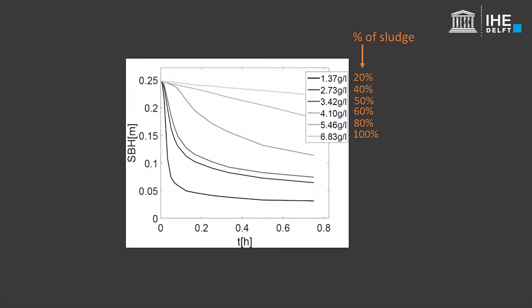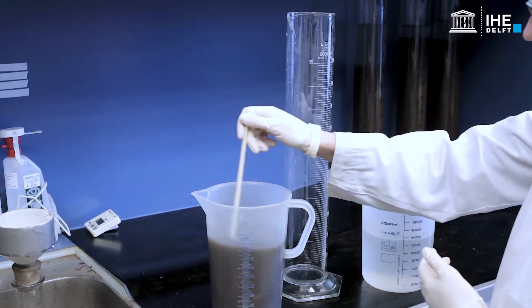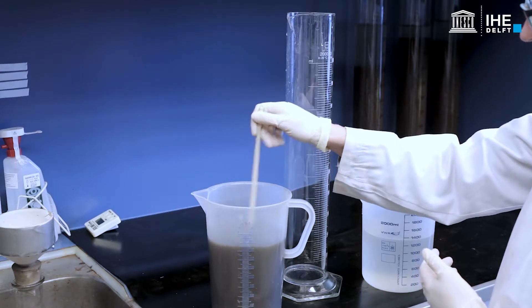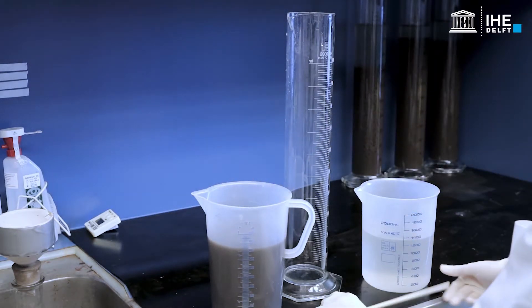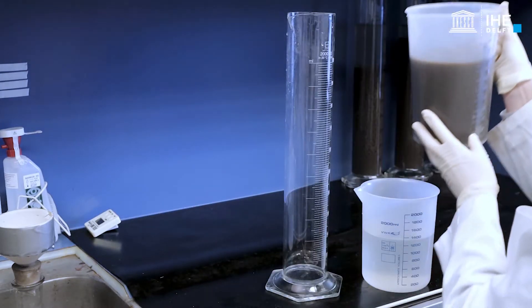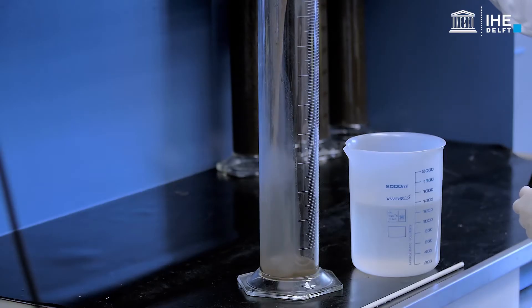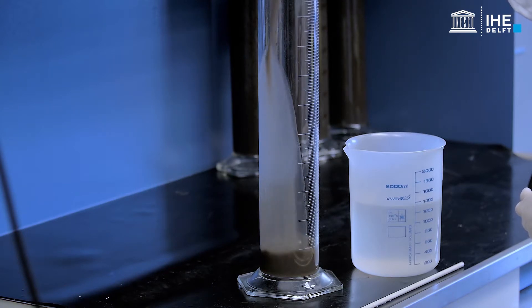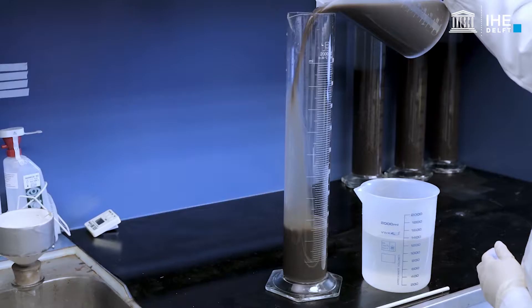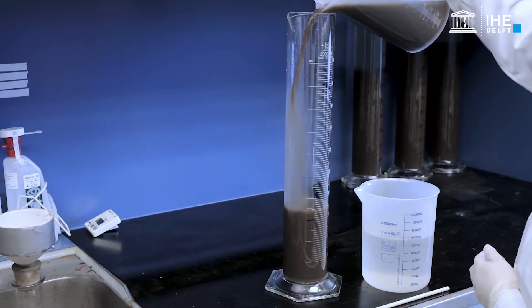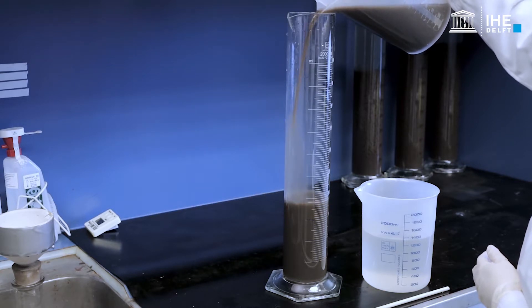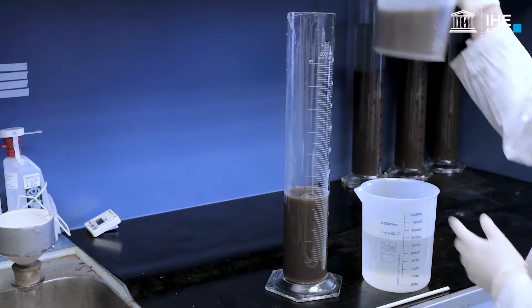To investigate the relation between settling velocity and sludge concentration, batch settling curves can be measured for a dilution series. A dilution series is made by diluting or concentrating sludge from return flow with effluent. For a 40% dilution, pour 800 millilitres of sludge into a 2 litre column and then fill the remaining space with effluent.